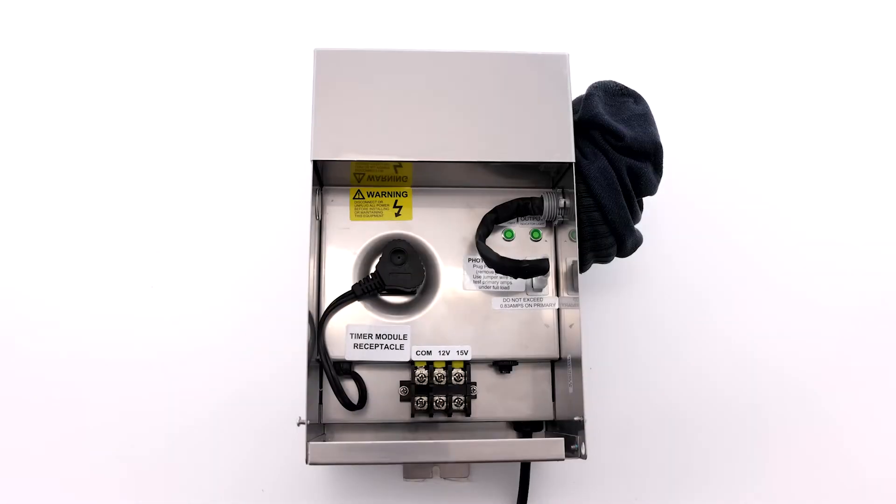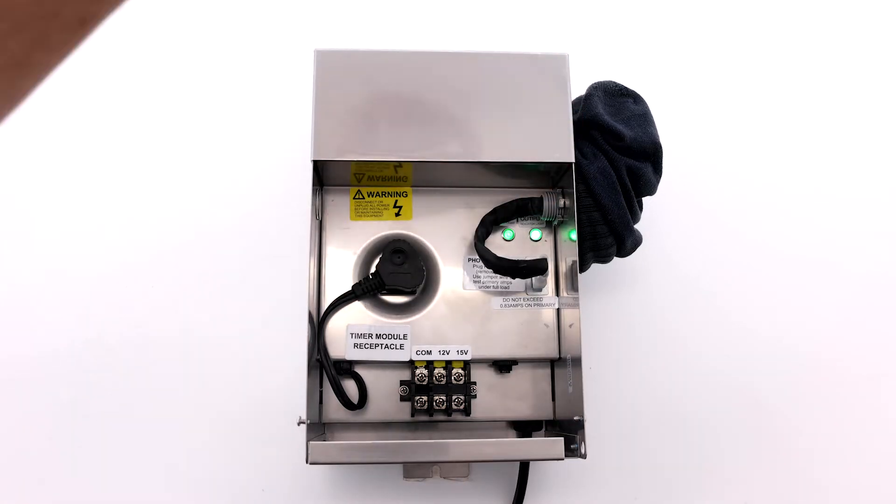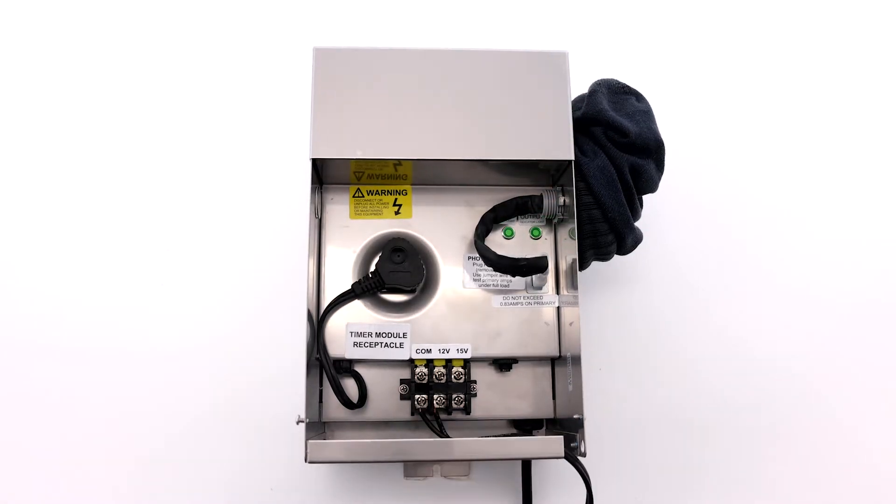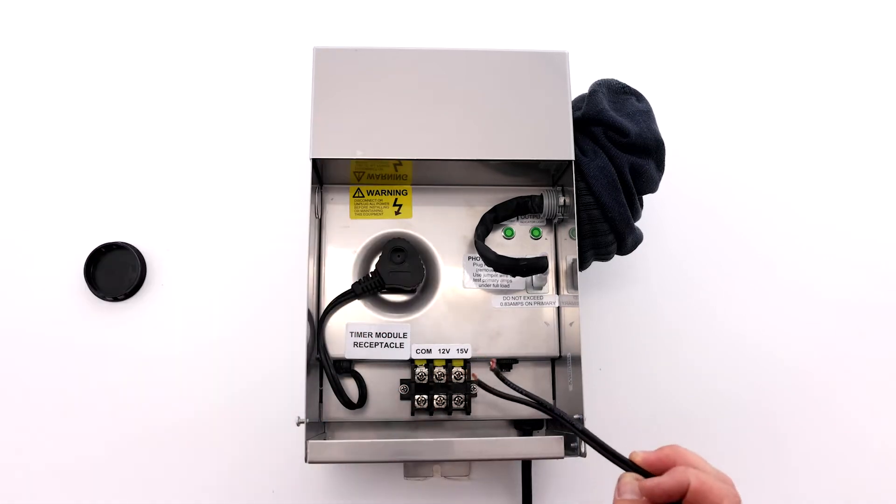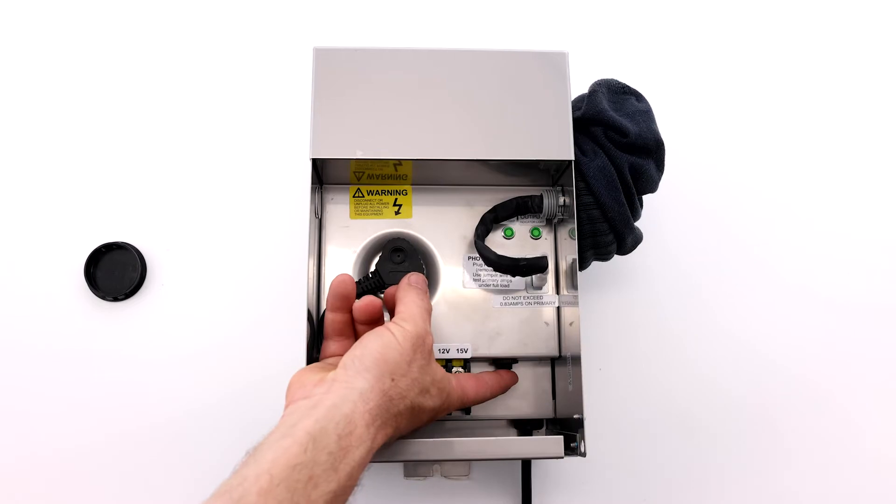Once the photocell is installed, with the photocell completely covered, the plug installed in the socket and power to the transformer, both indicator lights should come on. And if not, and there is a load attached, remove the load wires, check the breaker, and try again.